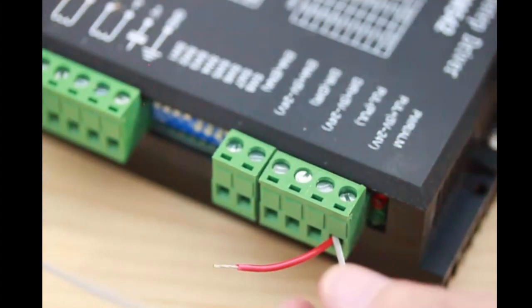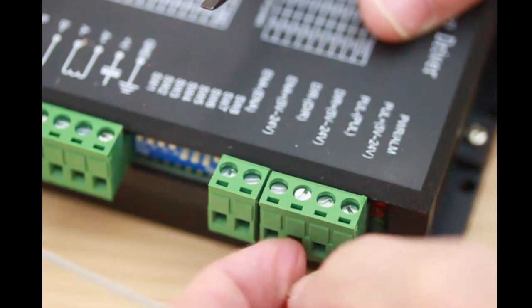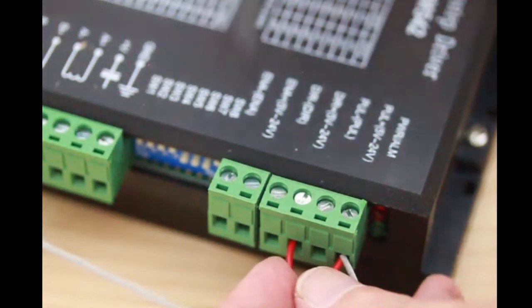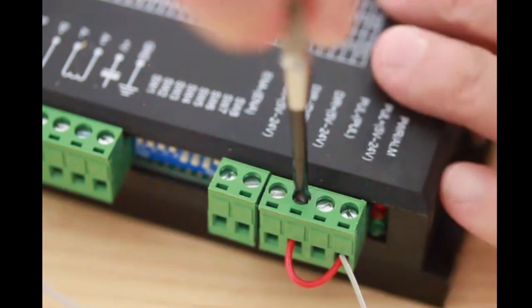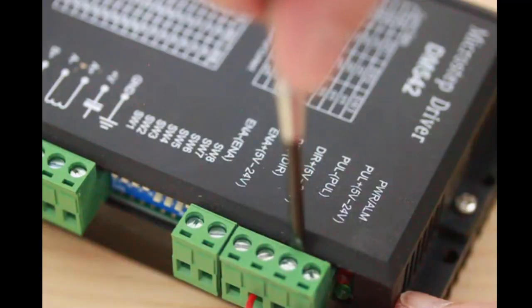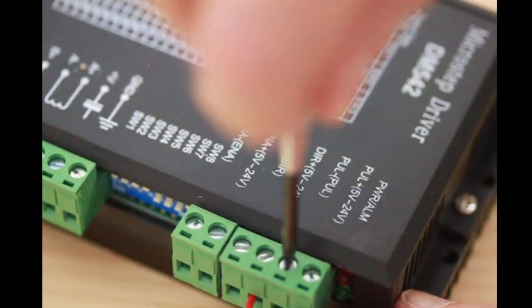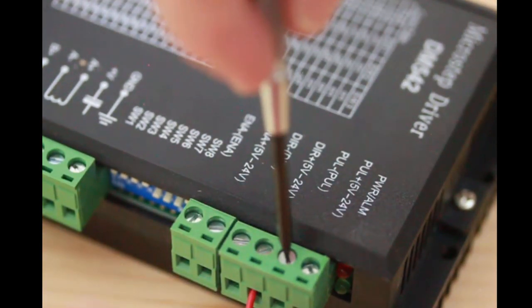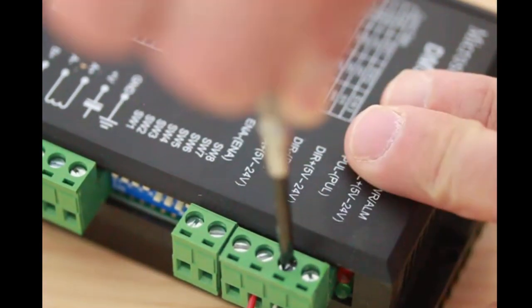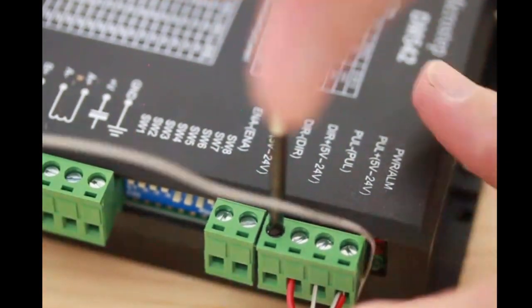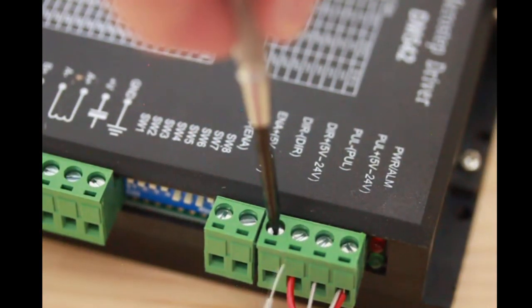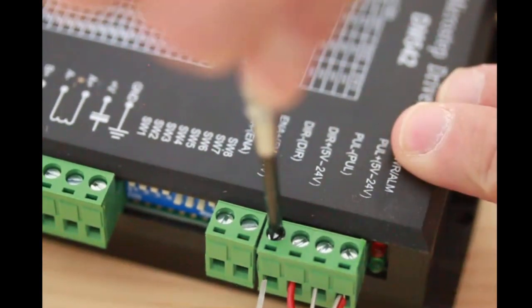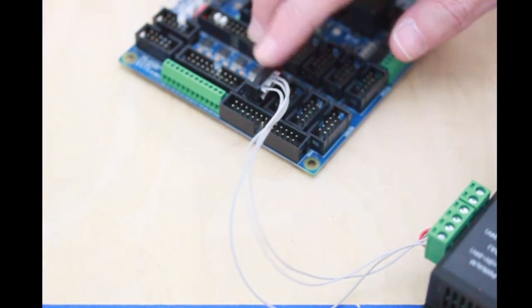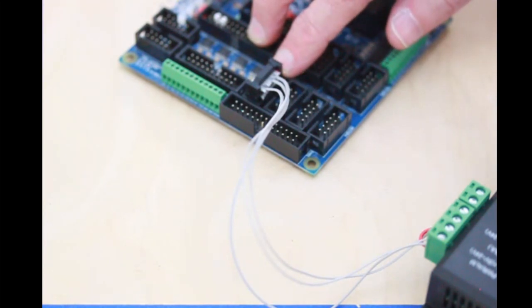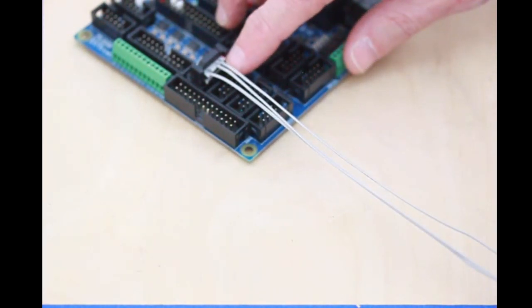These terminals may be called CP for pulse and CW for direction, depending on what driver you have. Conductor number 5 will be inserted into the PUL or pulse negative terminal. And now I will insert the conductor number 3 into the direction negative terminal. This is what the final assembled connection should look like, connected into the terminal and going straight to the driver.